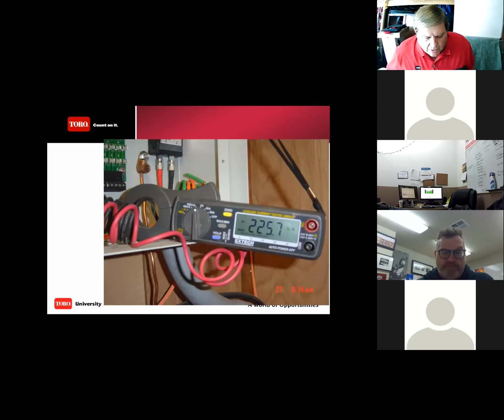That's all you're doing. So here I'm starting at the clock and I'm reading 225.7 milliamps. That is high. That's incredibly high. Not enough to blow the fuse, but it's high. And I got to stop right here because this is a perfectly good spot to do this. If you're blowing the fuse on the clock, we need to figure out, is it because you have a bad board or do you have a bad 2-wire path? Remove the 2-wire path from the system, replace the fuse and see if the fuse blows again. If the fuse blows again, then you got a bad 2-wire board in the controller. If the fuse doesn't blow, next step, I do this.